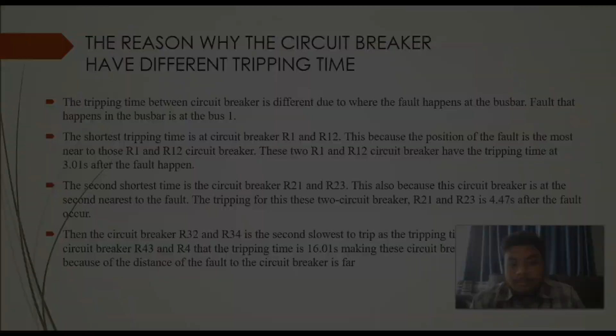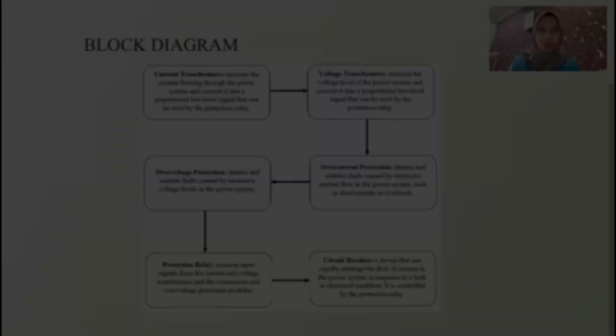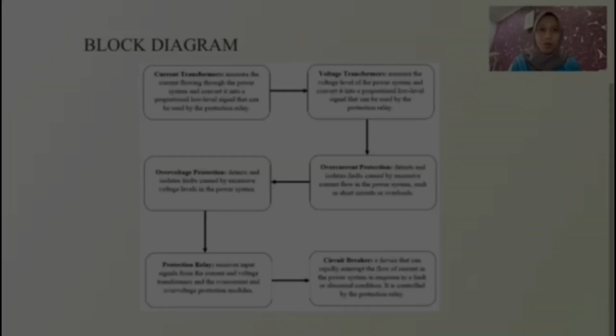And next, the second shortest time is R21 and R23 with 4.47 second after the fault occurs. Then the circuit breakers R32 and R34 are the next to trip, as the tripping time is 7.34 second. Then the circuit breakers R43 and R4 have a tripping time of 16.01 second, which makes them the last to trip because the distance of the fault to the circuit breaker is far.